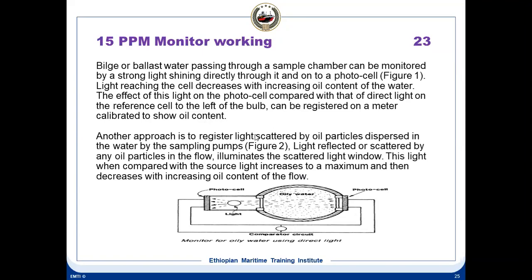Another approach is to register light scattered by oil particles dispersed in the water by sampling pumps. Light reflected or scattered by any oil particle in the flow illuminates the scattered light window. So this is the ideal one. You can draw this diagram if asked: what is the basic principle of a 15 ppm monitor? This diagram is good enough to explain this.